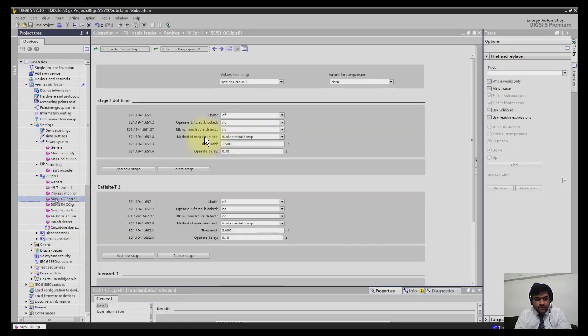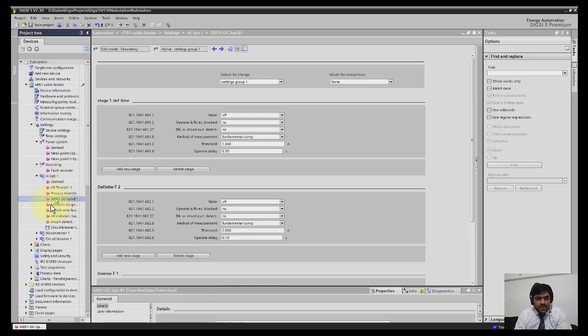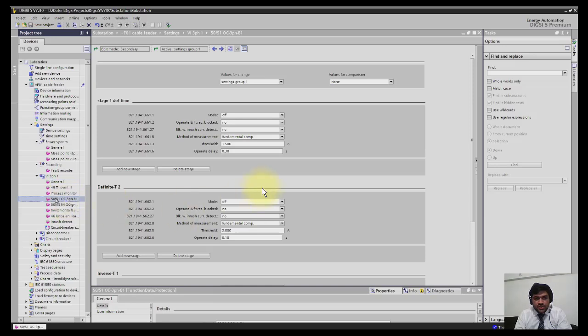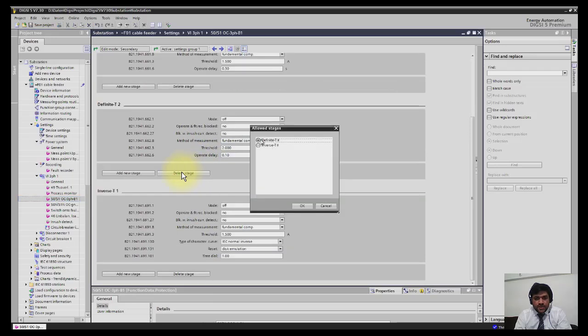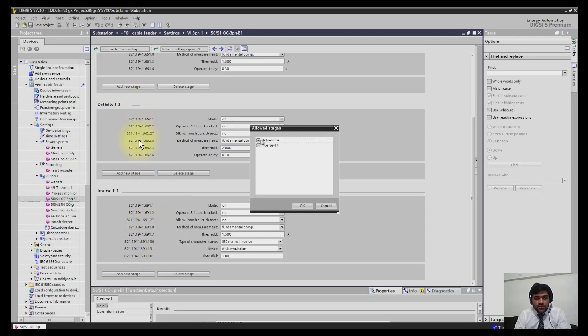Here you can see if you select three-phase voltage and three-phase current, it has a built-in function that can operate. I select this 50 overcurrent function and here you can easily define certain settings of this function. One more thing I want to add: the number of stages shown are not fixed.